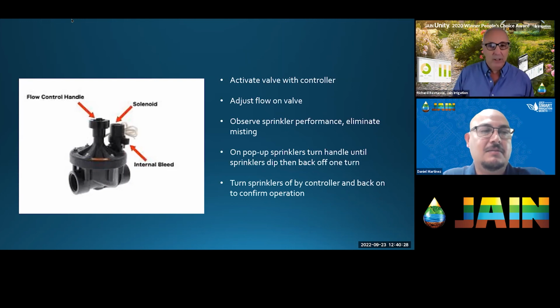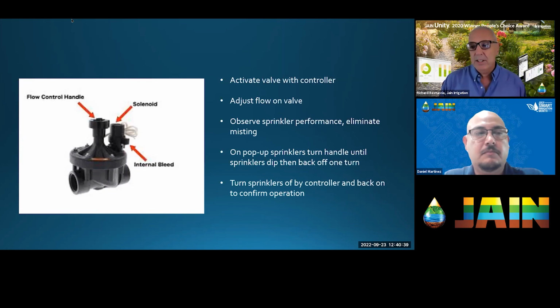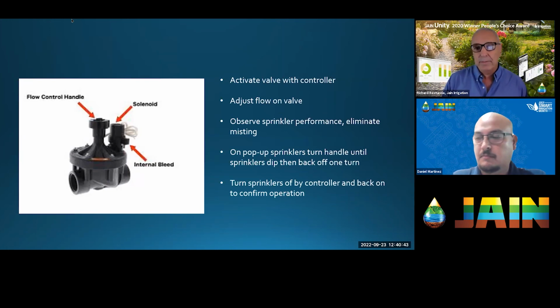So if I back down to a 1.5-inch valve or an inch valve, I'll see that I'm within the spec. Yes, correct, Richard. And then somebody else is making the comment, would it be easier to install a pressure regulator instead of changing a valve in that situation? Yes, definitely. Sometimes you may need to do both, right?